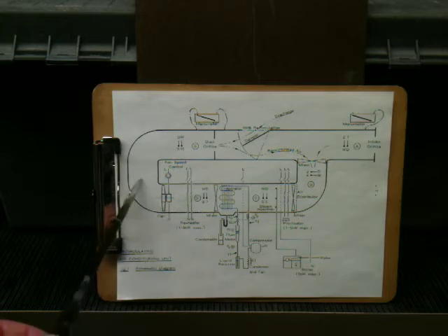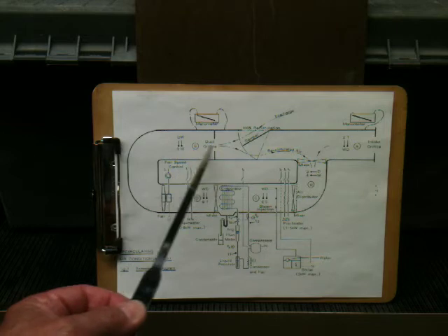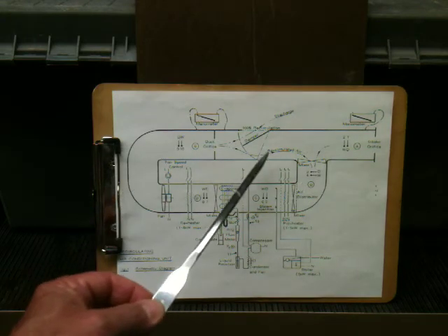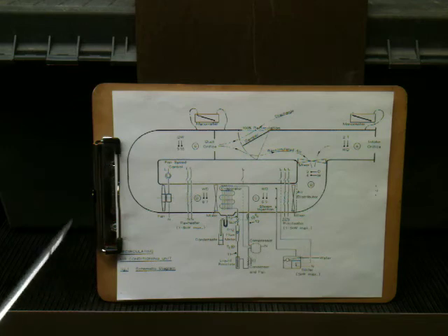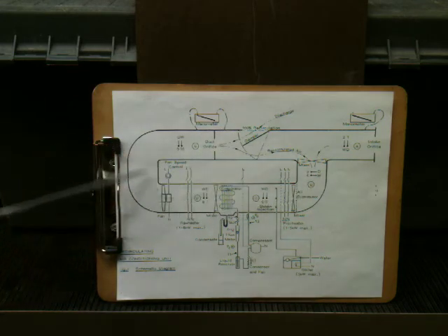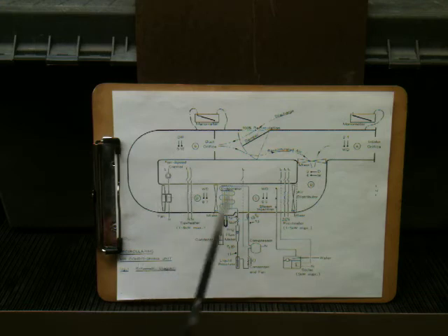Here is the fan, so then the air flows upward past station E, and then out through the damper into the lab. So for most of the tests, we're just going in through the intake. We go one pass through the unit, and then out through the damper. Then for test number 6, we actually partially close the damper so that we're recirculating the air. And again, we're still adding steam through the injector, and we're adding heat through the reheater. We're also cooling through the evaporator. So there's kind of a lot going on in that last test.